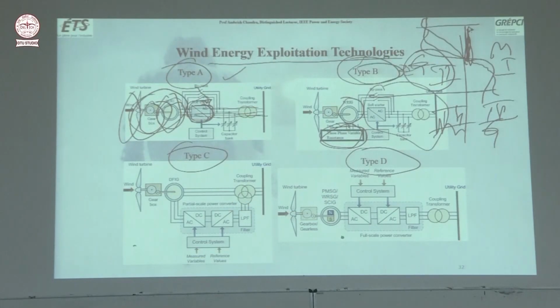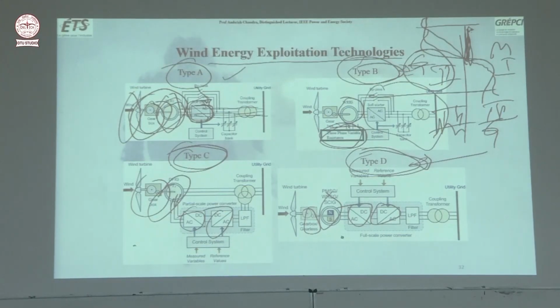So this is type B. Then type C we have already discussed yesterday, doubly fed induction generator with gearbox and then back-to-back converter of one-third capacity on the rotor side. This we have discussed. And then type D is the permanent magnet PMSG machine, where you don't have to use a gearbox, but you have to have a full-size back-to-back converter connected on the stator of the machine, and it gives very good performance, though it is costly. But you can have full fault ride-through capability, low voltage and high voltage ride-through, because it is totally decoupled due to the back-to-back full-size converters.